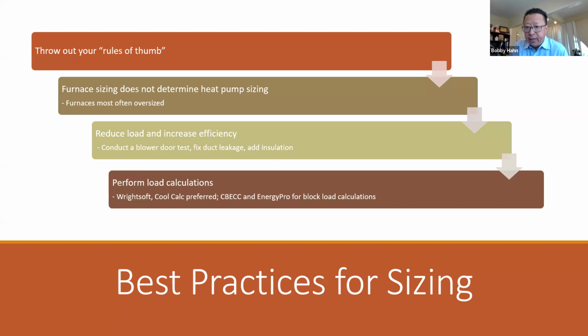Okay, there are heat pumps available in very small units for ADUs that are, say, 200 square foot. You'll take your load calculations, and you're going to want to size it to 200 square foot, depending on your solar exposure and your insulation, but you will want to model it to 200 square foot. Inverters can go down to 13% of their capacity, but that doesn't mean you want to oversize. You want to get as close as you can. There are 6,000 BTU mini splits out there, so that'd probably be pretty close for sizing in your area. You may want to take a look at that for your 200 square foot spot.